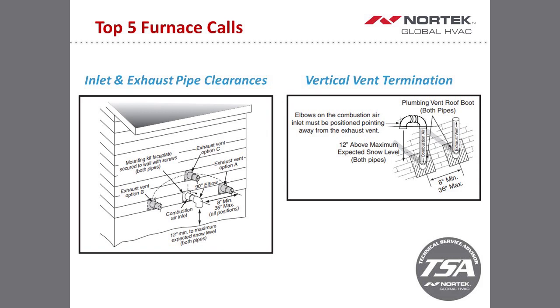What I have here are 2 pictures directly from our install instructions. On the left-hand side is if you were to bring your piping outside on a horizontal application, so that's coming out the side of a home or a building. And then the one on the right is if you're going through the roof. Really what I'll say here is that the minimum distance you can have between your intake and an exhaust pipe is 8 inches, and then the maximum is 36. So that's your range on where the PVC pipe can be.